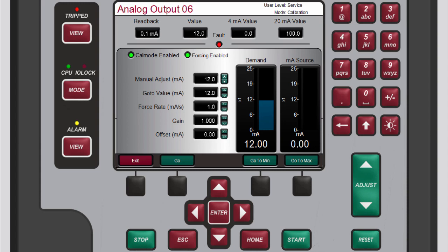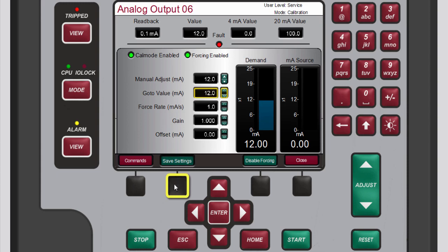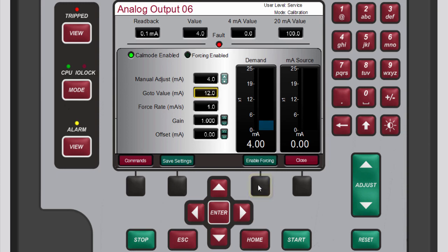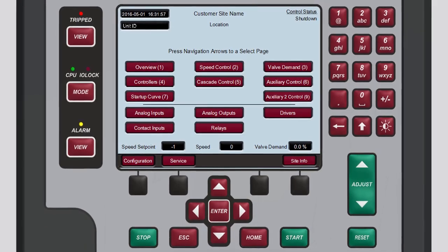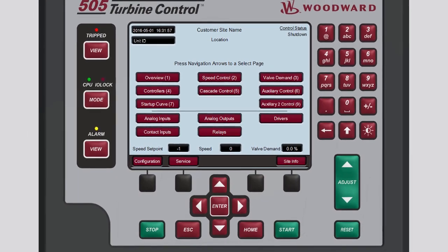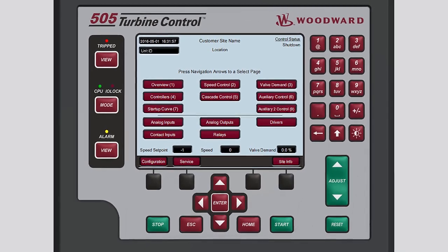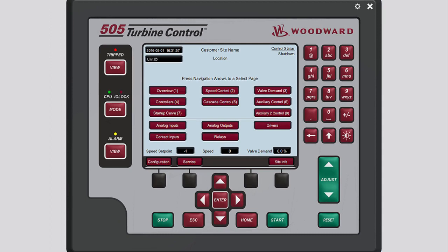When you are done forcing outputs, press the black function key below exit. If you made changes, press the black function key below save settings. Then disable the forcing by pressing the black function key below disable forcing. Now close the pop-up window by pressing the black function key below close. Remember to exit calibration mode. You now know the basics of the configuration and calibration of analog output logic. Please be sure to view the other tutorials for more information.